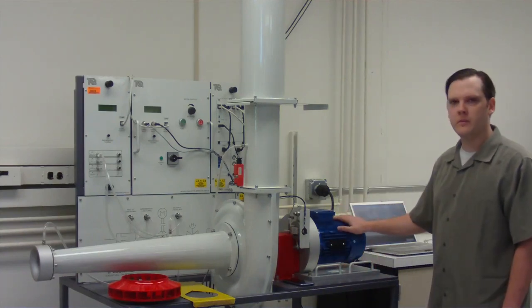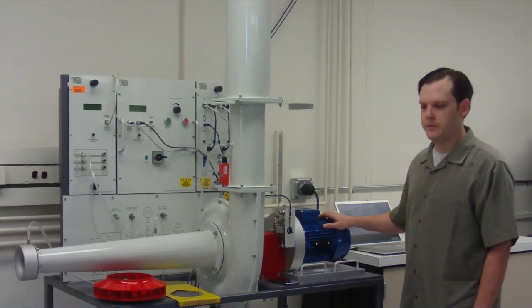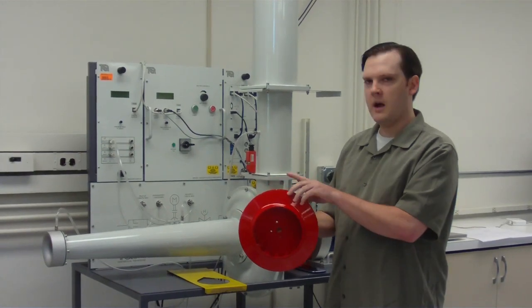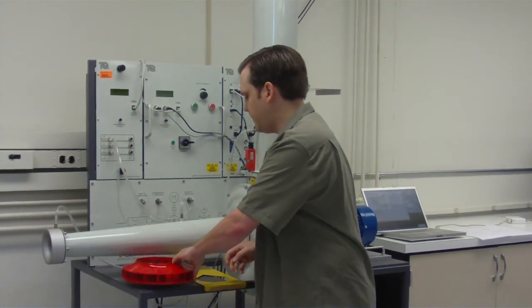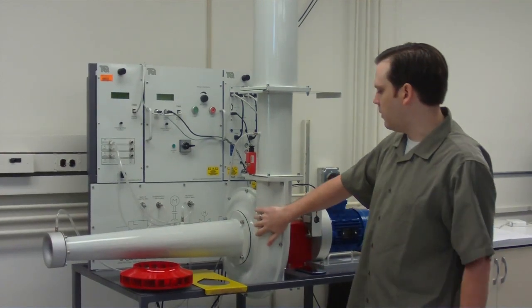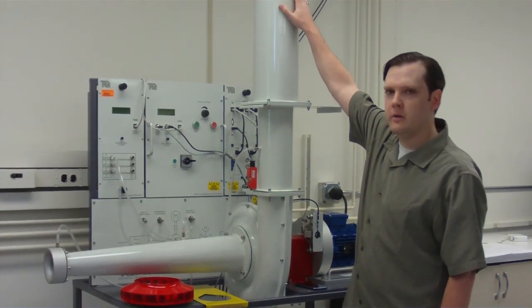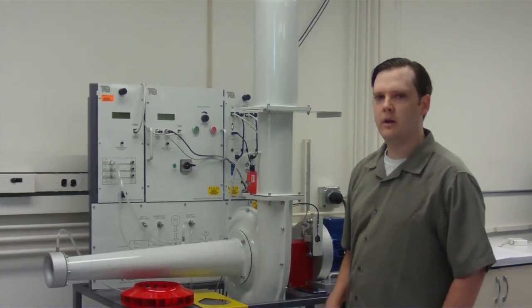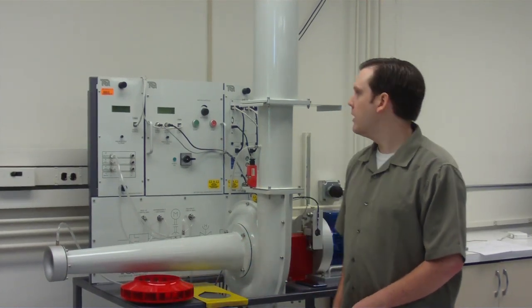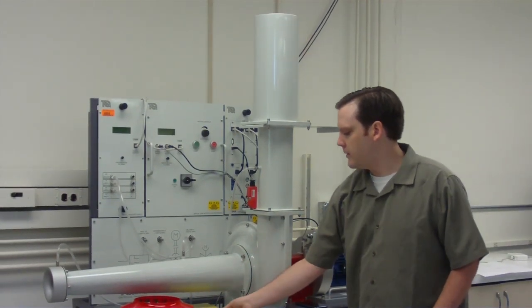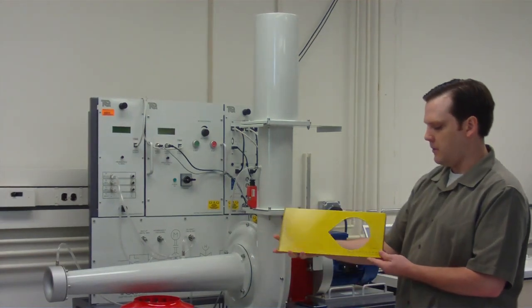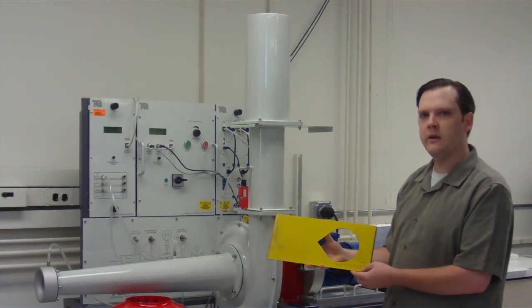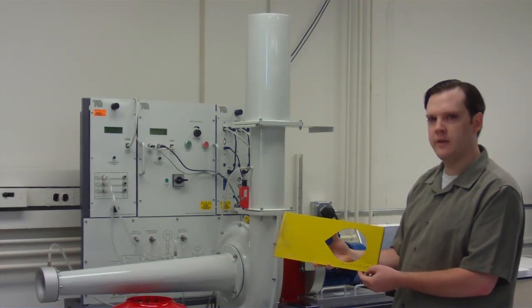This is a drive motor. It drives the impeller at a one-to-one ratio. As the impeller rotates, it takes air from the inlet and flings it out radially through the outlet. The fluid gathers in the scroll and exits at areas of lower pressure, mainly the exhaust here, but some of it does recirculate back through the gaps in the scroll into the inlet of the impeller once again. Before air exits the exhaust here, it passes through a specially shaped and incremented slide plate. This allows you to control the airflow through the exhaust by the percentage of the area open.